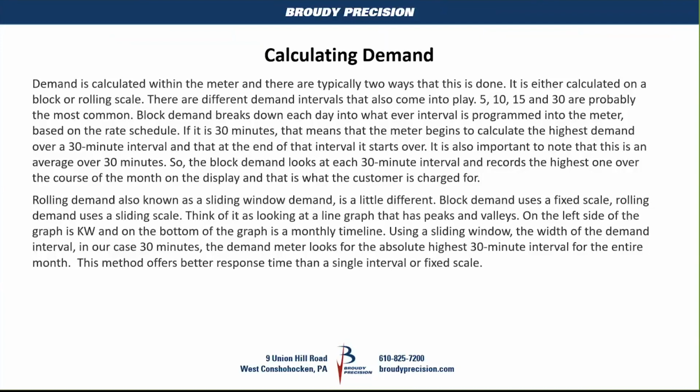So the best thing that we do in the energy saving aspect of this is we essentially take a half an hour or a 15-minute sliding window, and we may or may not be in the scale of the utility, but we're still counting the pulses or the kilowatts that come in that interval.